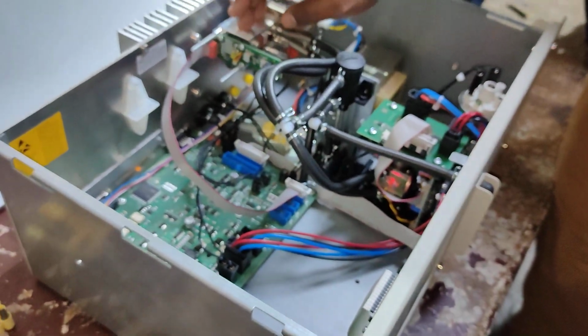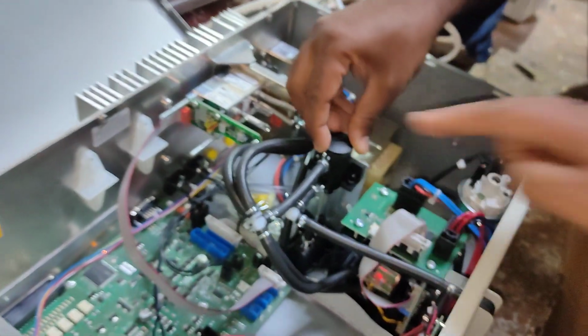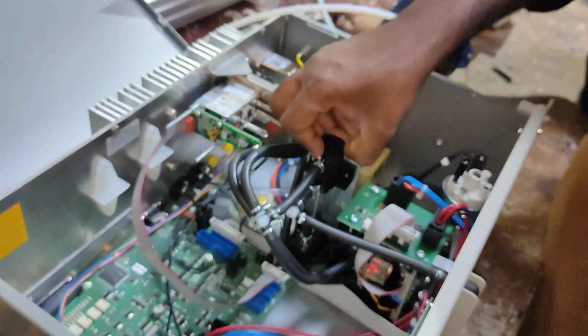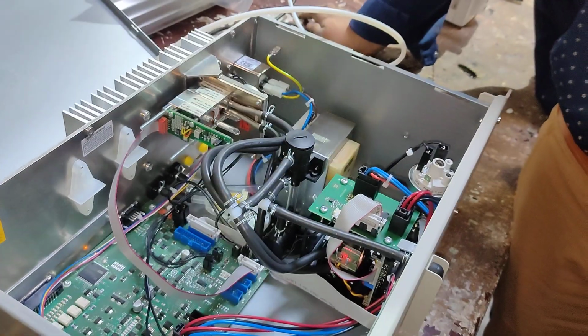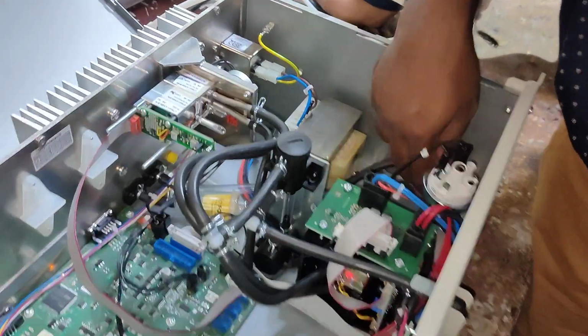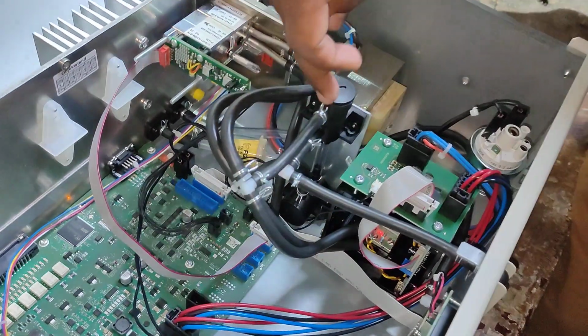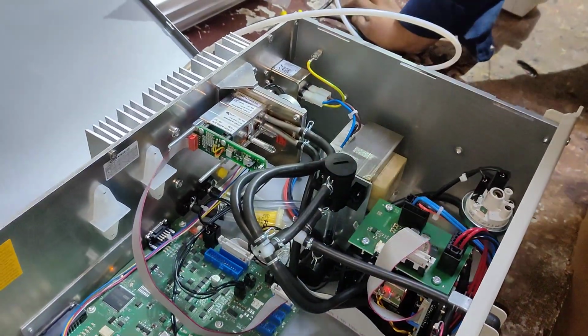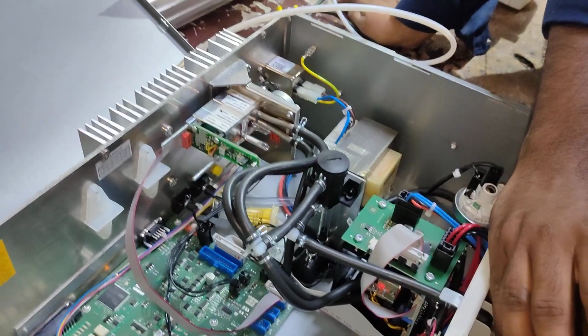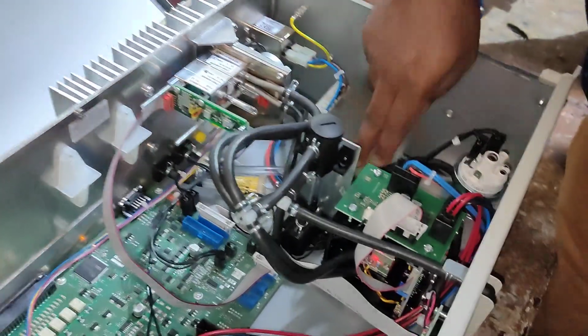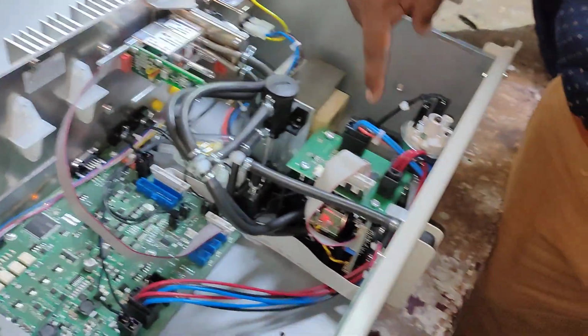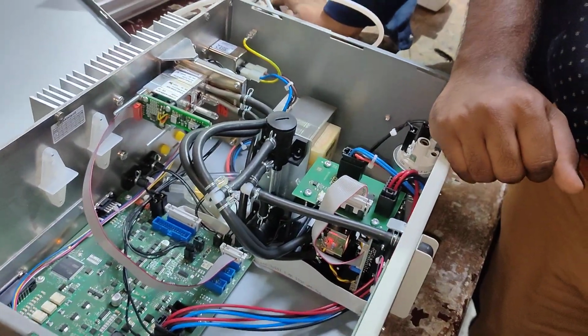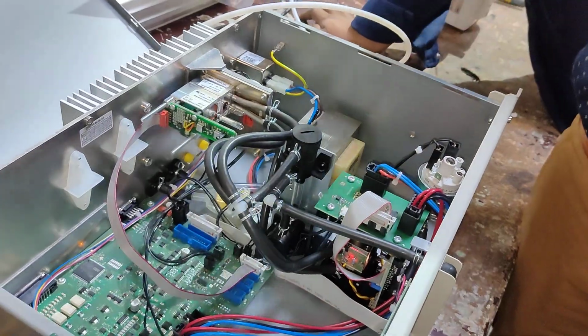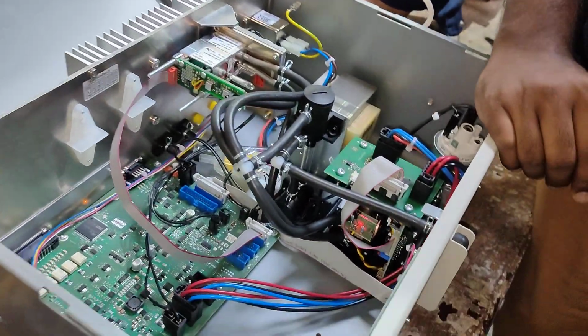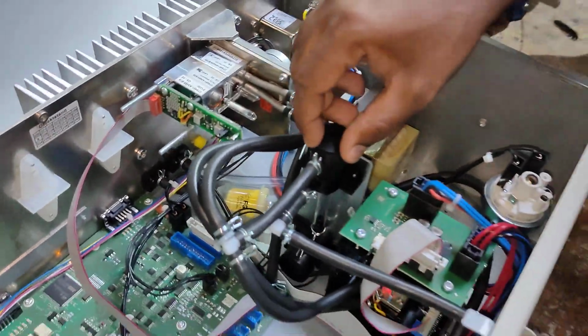And what is this black color one in the center? It's a condenser. If in your sample you are getting water condensate, the sample will first go through the sample flow meter and then through this condenser. Based on gravity, the water will drop down, and the outlet of this is connected outside at the sample out, the big tube. So we need to take it out. That will go out by itself, so to the maximum extent it will avoid any water going inside.